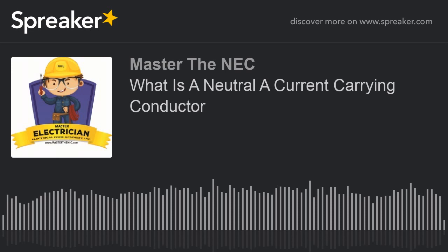Now, I can't really get any more detailed than that. The engineer who's designing the system should make it clear. It should be crystal clear that if it is a 3-wire circuit, consisting of 2-phase conductors and a neutral, and of course it could have an equipment ground as well, but it is 3-wire, 2-phase conductors and a neutral, deriving from a 4-wire 3-phase Y-connected system. If they're doing that, then that neutral conductor is going to carry approximately the same amount of current.